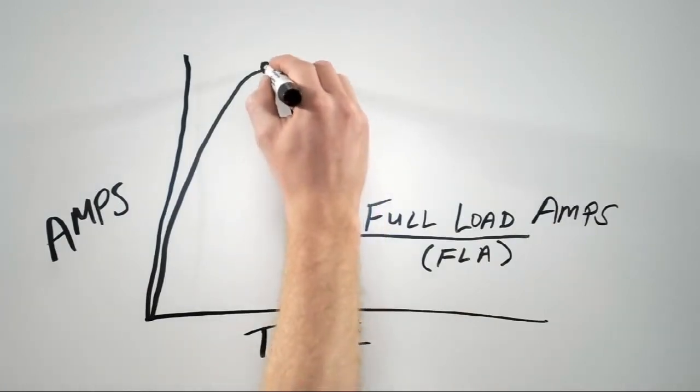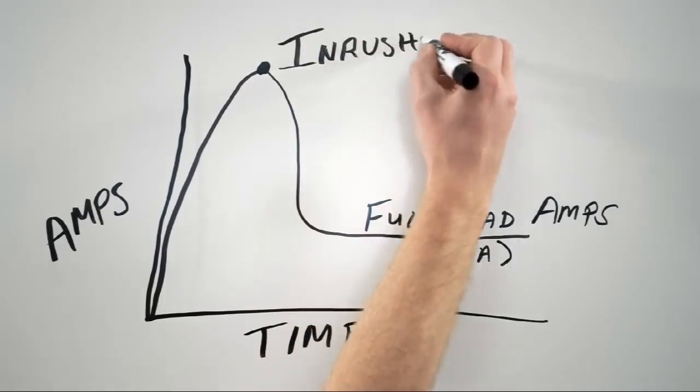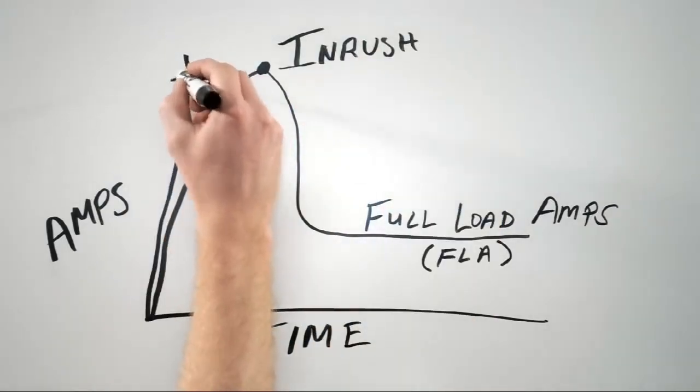That big spike of current you get when you start the motor is called inrush. Inrush is usually about 6 to 8 times the full load amps of the motor.